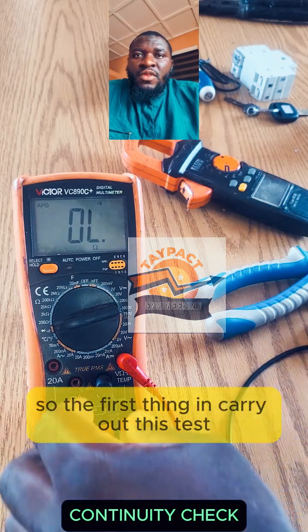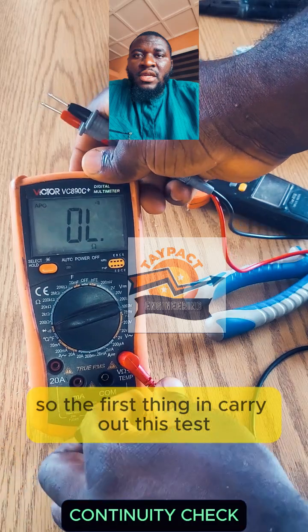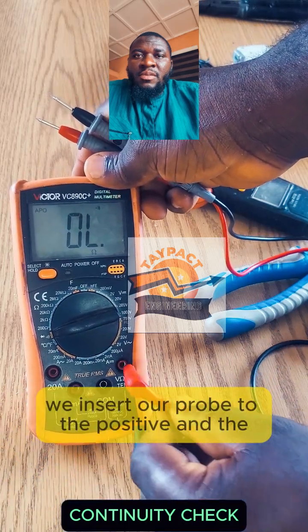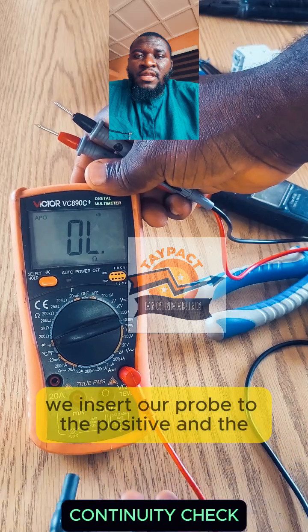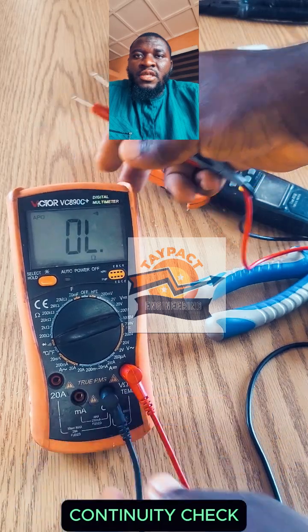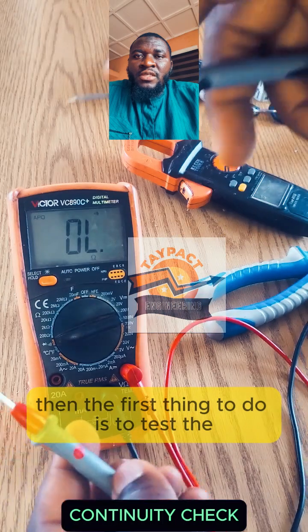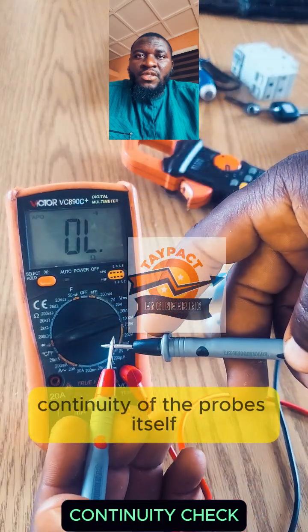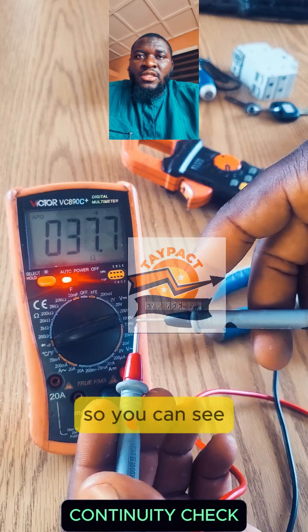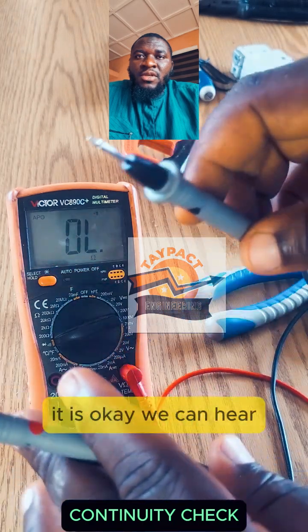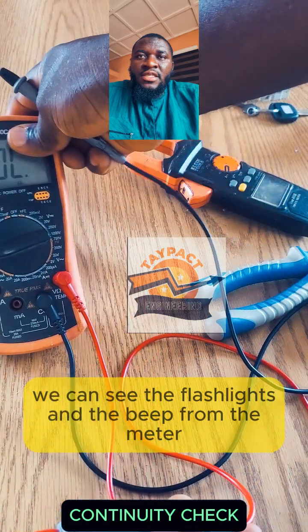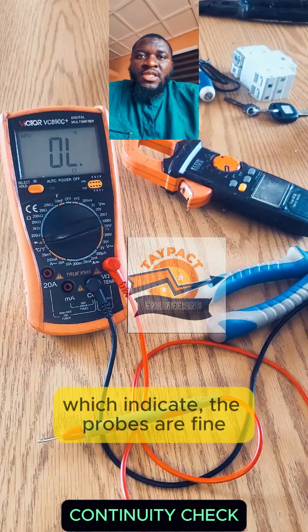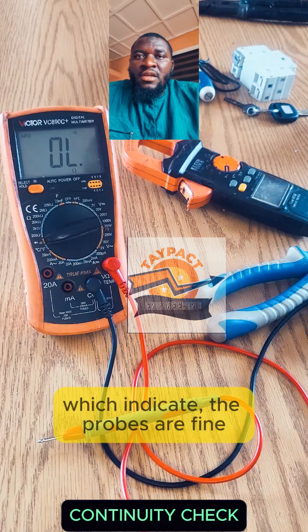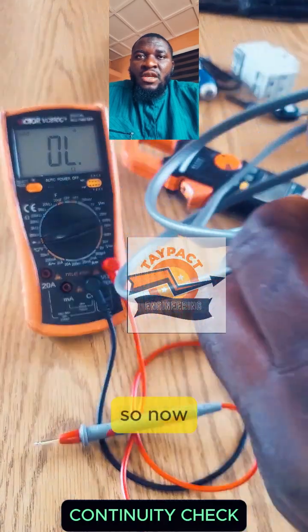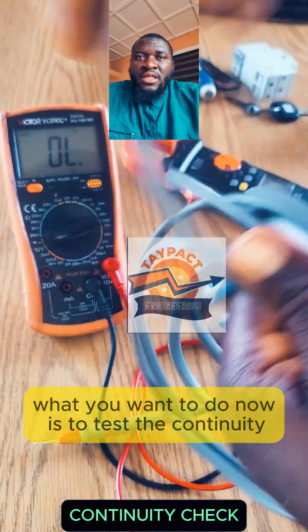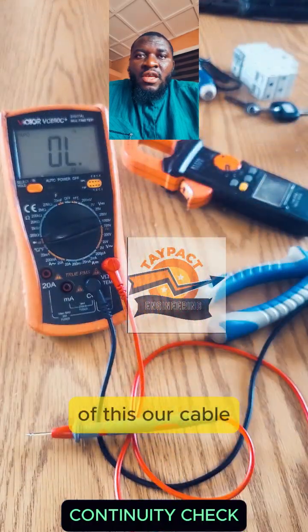So the first thing in carrying out this test, we insert our probes into the positive and the COM positions. Then the first thing to do is to test the continuity of the probes themselves by linking them together. So you can see we've tested them, it is okay. We can see the flashlight and the beep from the meter, which indicates the probes are fine.